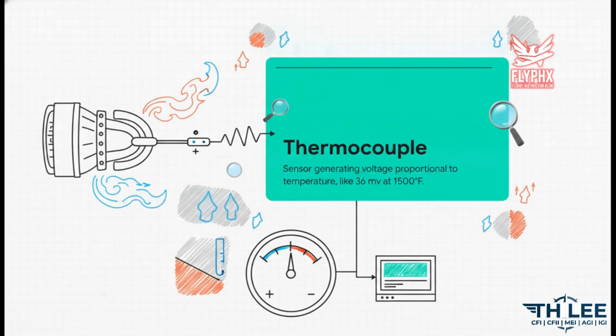The absolute secret behind that gauge on your panel is the thermocouple. A thermocouple is simply a sensor that generates a remarkably tiny voltage strictly proportional to the temperature right at the probe itself. To give you some real-world perspective here, a typical EGT at cruise runs right around 1500 degrees Fahrenheit. At that intense, blistering heat, the probe is generating a mere 36 millivolts. That's 0.036 volts, practically nothing.